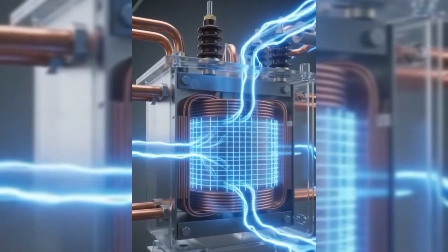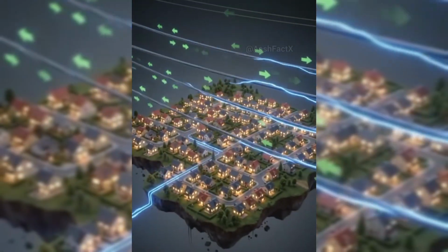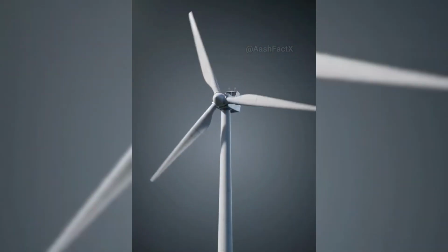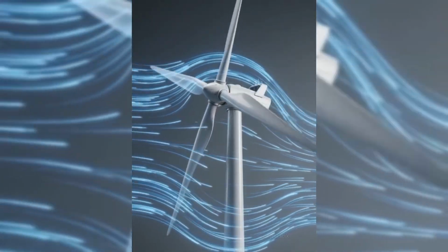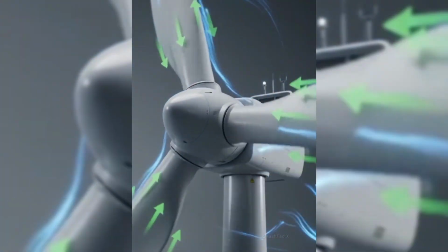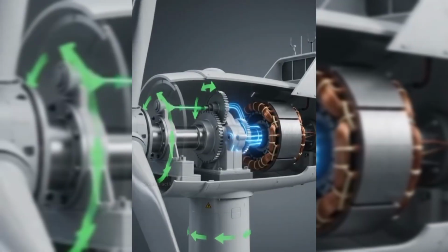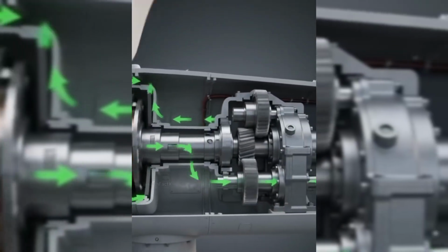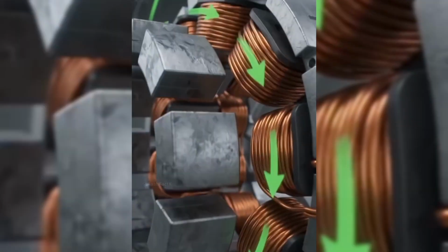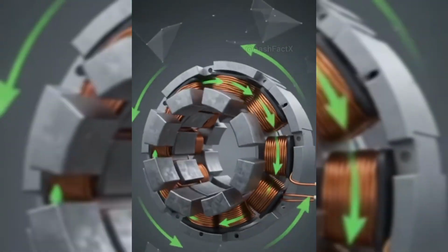To resolve this mechanical challenge, the low-speed shaft feeds into a heavy-duty gearbox. The gearbox acts as a mechanical amplifier, dramatically increasing the rotational speed. By utilizing a precise arrangement of internal gears, it converts the slow, high-torque rotation of the main shaft into a high-speed rotation reaching roughly 1500 to 1800 revolutions per minute. This high-speed shaft is then connected directly to the generator.